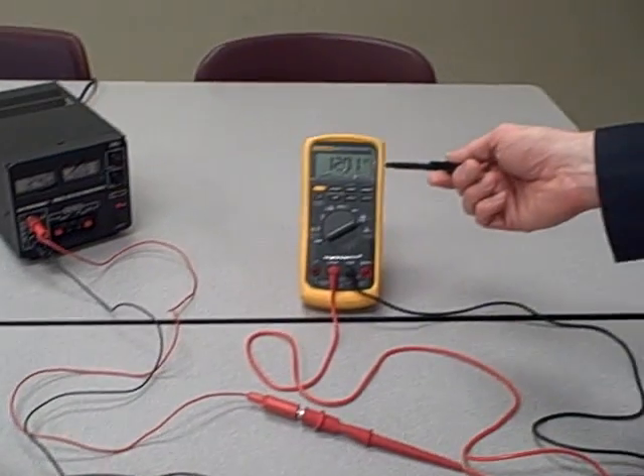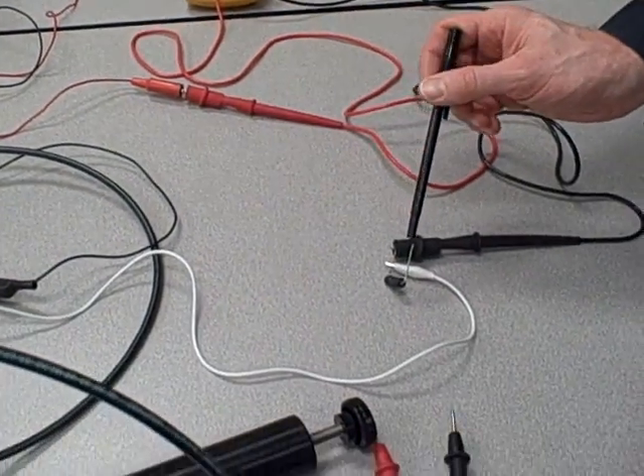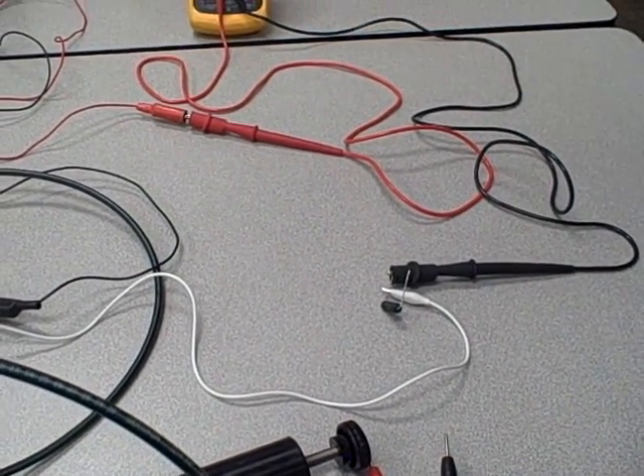And my current is unchanged. So as we've seen before, the presence or absence of a resistance in the DC circuit really doesn't affect the basic 4 to 20 milliamp analog signal at all.